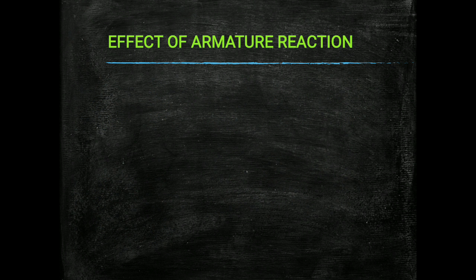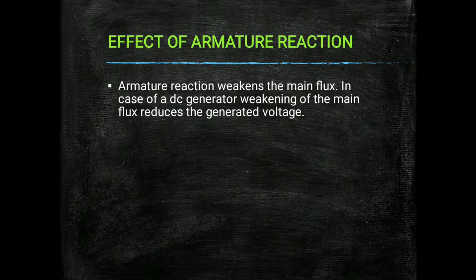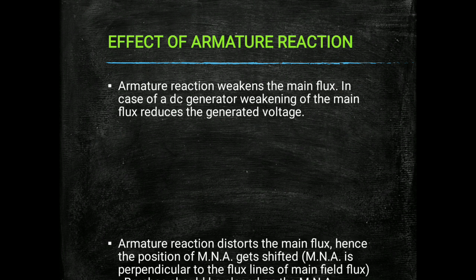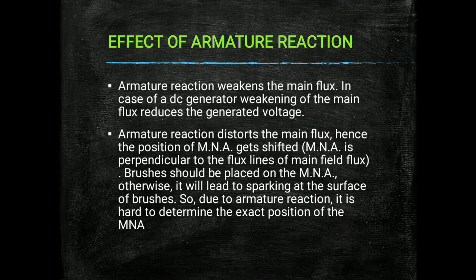The effects of armature reaction are as follows. First, armature reaction weakens the main flux because the armature flux opposes the main field flux. In a DC generator, weakening of the main flux reduces the generated voltage. Second, armature reaction distorts the main flux, and hence the position of the MNA gets shifted. As already stated, brushes should be placed on the MNA; otherwise it will lead to sparking at the surface of the brushes.